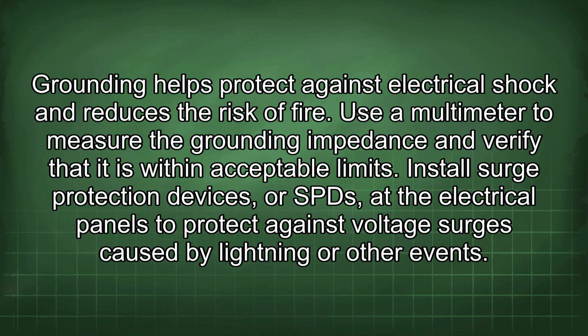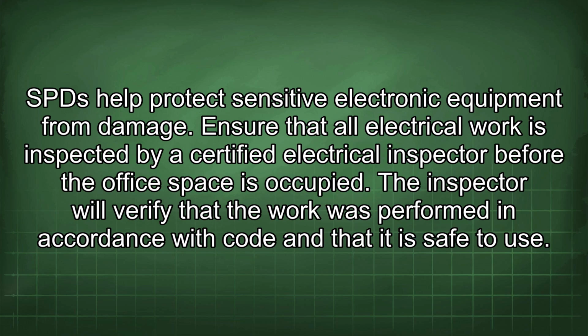Grounding helps protect against electrical shock and reduces the risk of fire. Use a multimeter to measure the grounding impedance and verify that it is within acceptable limits. Install surge protection devices, or SPDs, at the electrical panels to protect against voltage surges caused by lightning or other events. SPDs help protect sensitive electronic equipment from damage.